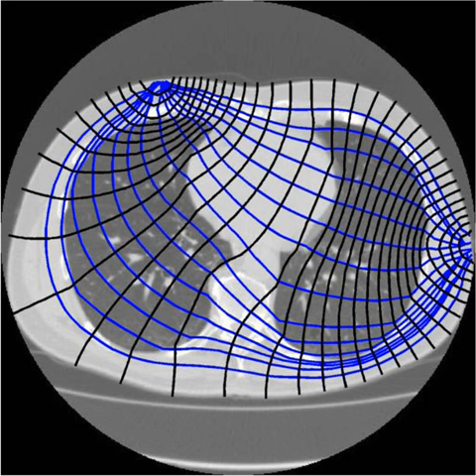After positioning surface electrodes through adhesive electrodes, an electrode belt or a conductive electrode vest around the body part of interest, alternating currents of typically a few milliamperes at a frequency of 10 to 100 kHz will be applied across two or more drive electrodes. The remaining electrodes will be used to measure the resulting voltage. The procedure will then be repeated for numerous stimulation patterns, e.g. successive pairs of adjacent electrodes until an entire circle has been completed and image reconstruction can be carried out and displayed by a digital workstation.